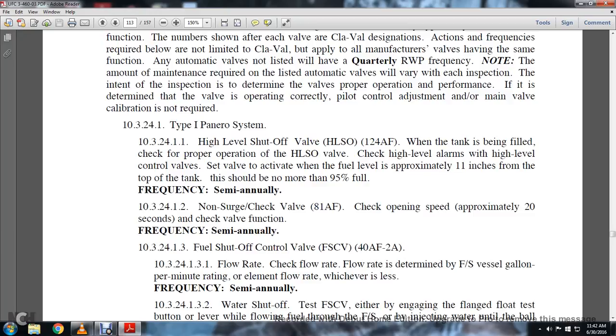324.1 Type 1 Panero high level shutoff valve, the HLSO valve 124 AF. When the tank is being filled, check the proper operation of the high level shutoff valve, and check the high level alarms and the high level control valves. Set the valve to activate at a fuel level approximately 11 inches from the top of the tank. This should be not more than 95% full. Check the high level shutoff valve, Type 1 Panero, semi-annually.